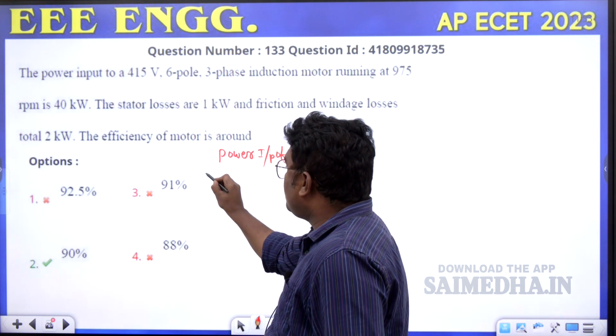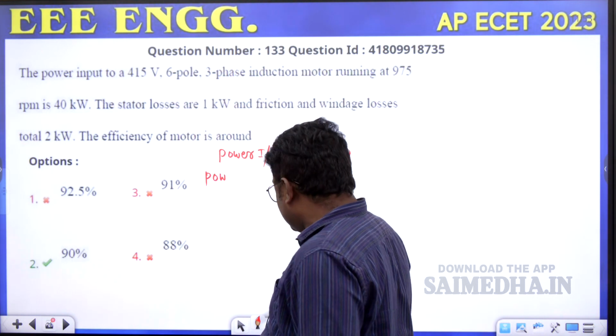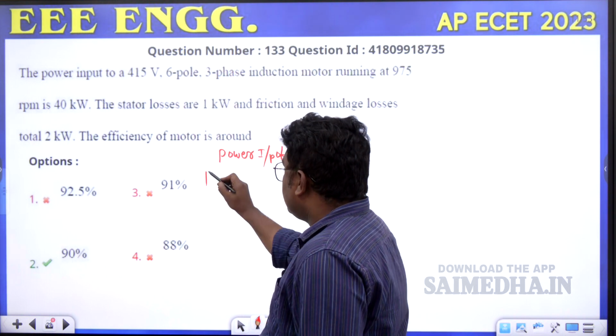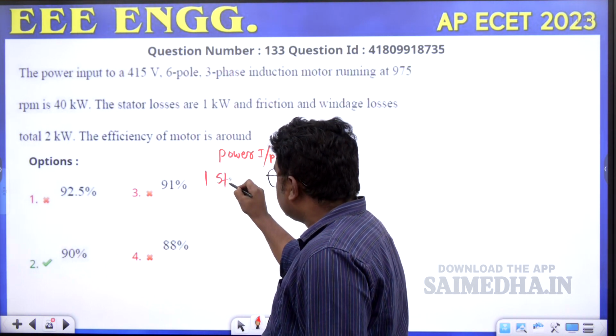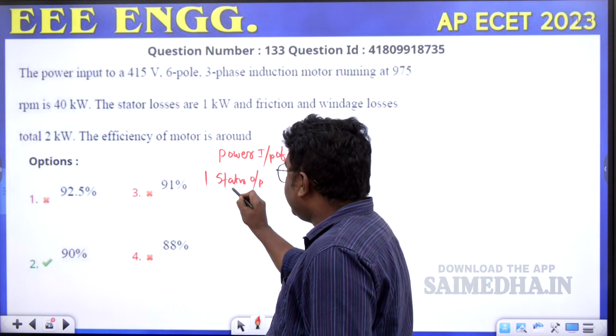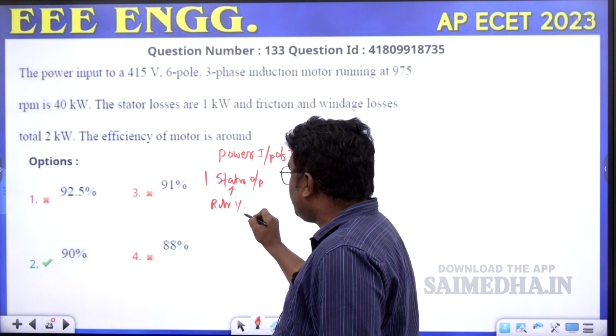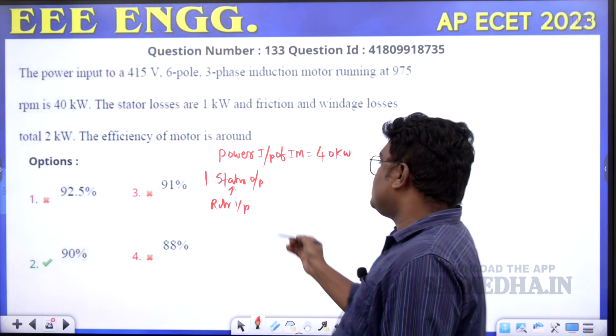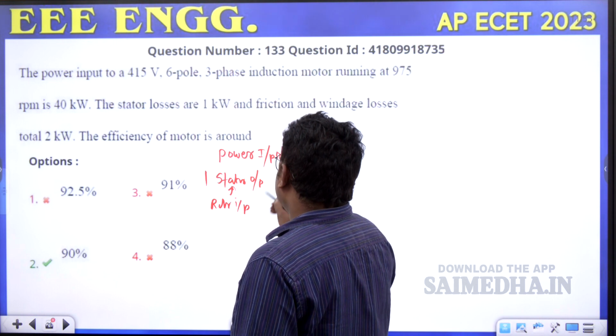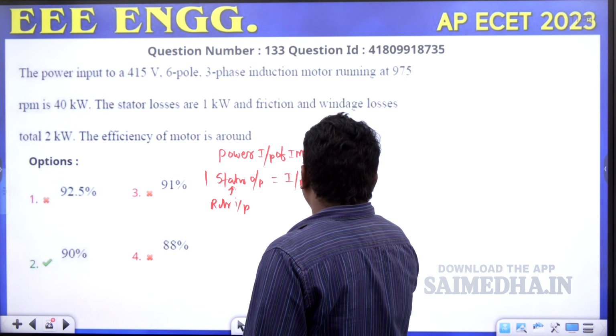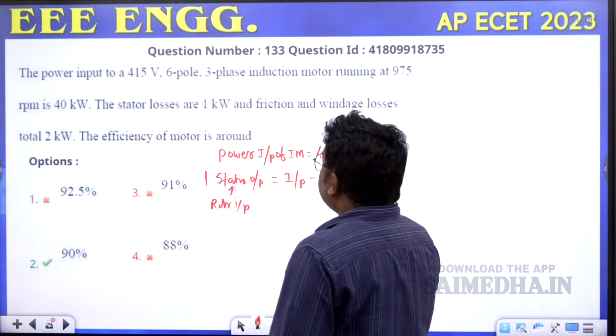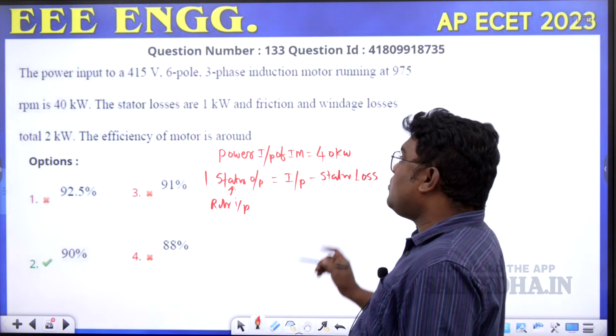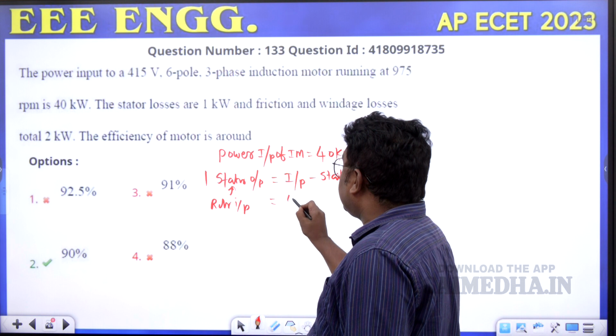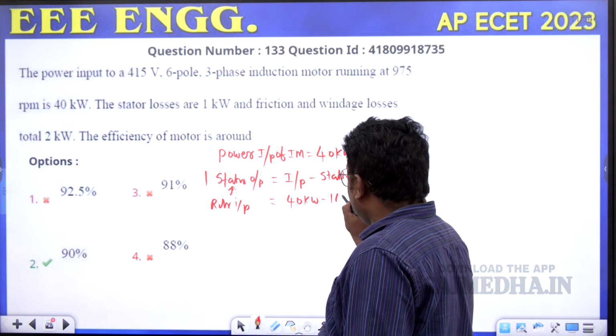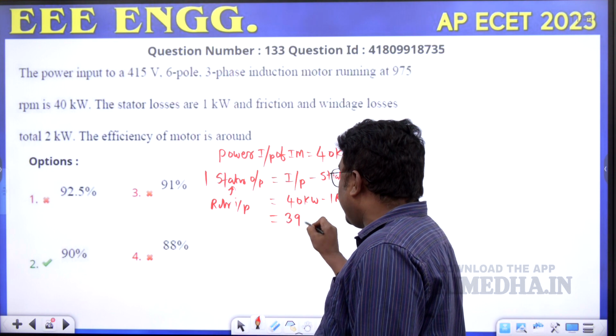Now the power output, it is also called... this is the power input here. The stator output power is also called the rotor input power or air gap power. So this is the rotor input power here. It is equal to the input power of the machine minus the stator losses. What are the stator losses? The stator losses are equal to 1 kilowatt. The input power is 40 kilowatts minus 1 kilowatt, which is equal to 39 kilowatts.